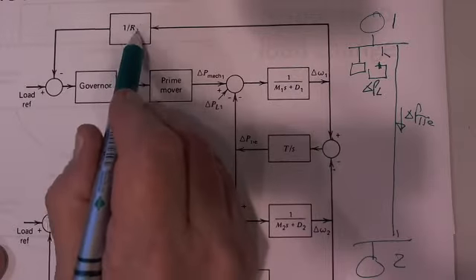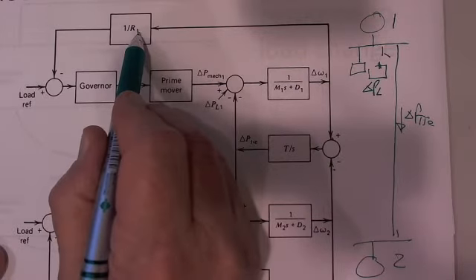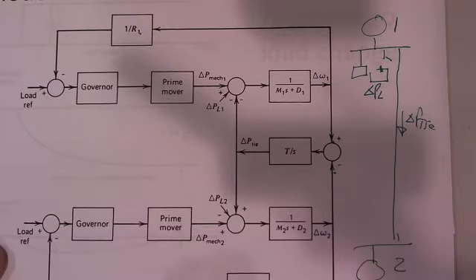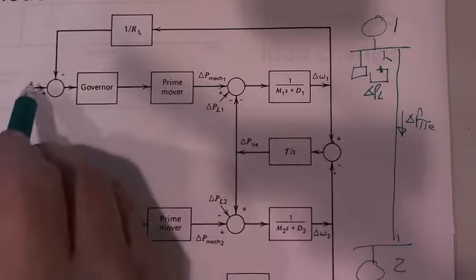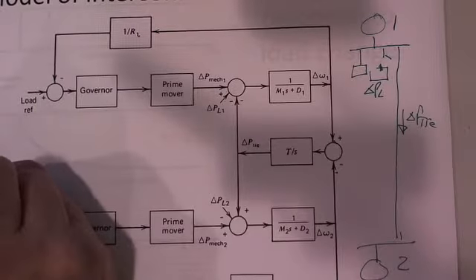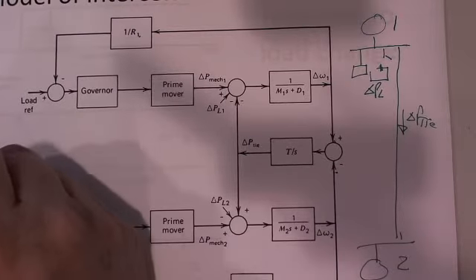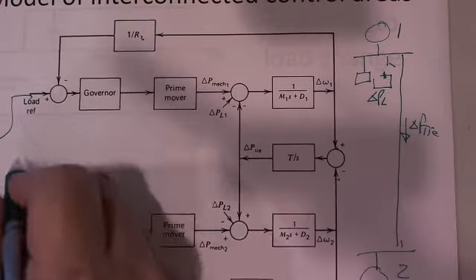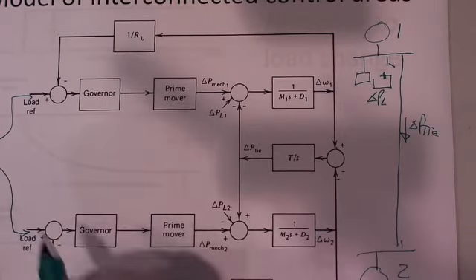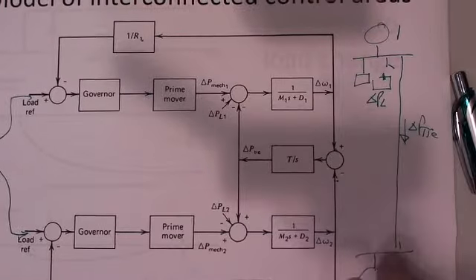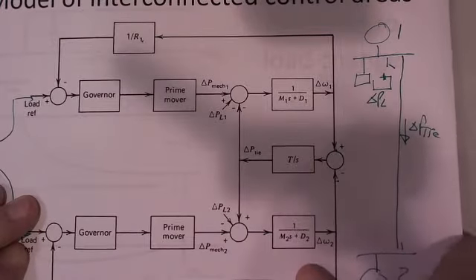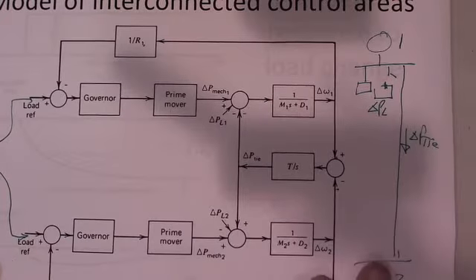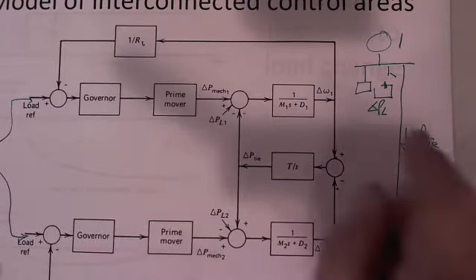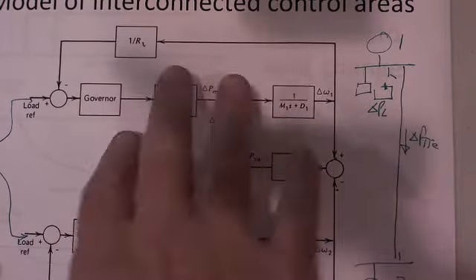Here's the slope, or the droop characteristic, for generator 1, and here's the droop characteristic for 2. The load reference set point comes from AGC in the control system, and it communicates this load reference set point here. That's the model we used in our undergraduate course. You can change the load, and you can watch the frequency change in each area. You can watch the tie line change.